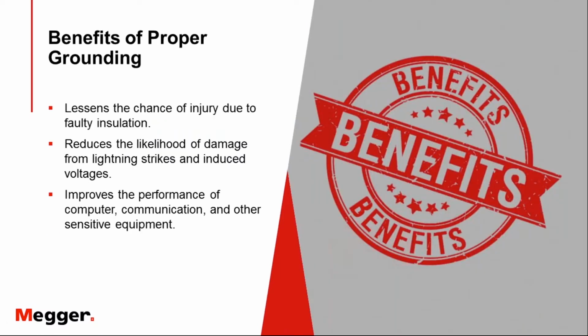As we said, injury prevention is really the most fundamental and important benefit of having a good ground, so that there's no place in your electrical facility where someone could touch something and get shocked. You want to make sure everything is in place, not only your grounding electrode but also your grounding conductors, all the way down to your ground bus, providing a very low impedance path so a human body doesn't look like a good current path by comparison.